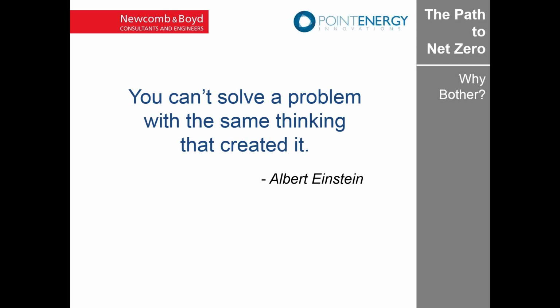You mentioned reducing friction energy in pump and fan systems. Have you done anything specifically towards that? Are you just talking about increasing the size of pipes and ductwork, or what have you been looking at? There's information out there about designing low pressure drop systems, using more efficient pumps and fans off the shelf, but more carefully selected. For example, I helped write the best practice guide from Labs 21 about low pressure drop design for laboratory air systems, and a lot of those concepts are transferable to office building HVAC systems. I'd recommend looking at that—it gives a snapshot of what we're talking about.